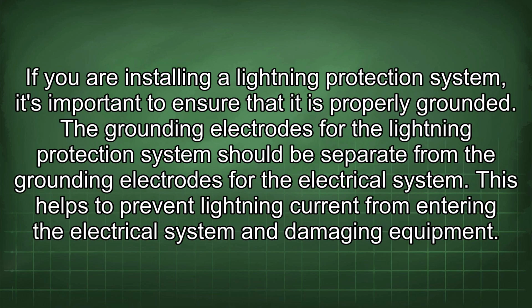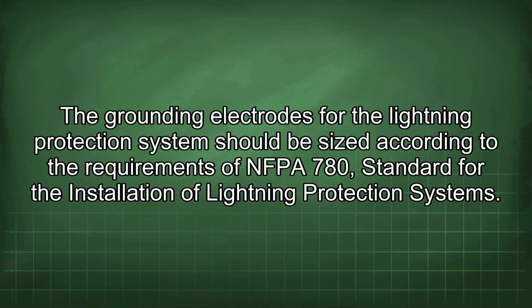If you are installing a lightning protection system, it's important to ensure that it is properly grounded. The grounding electrodes for the lightning protection system should be separate from the grounding electrodes for the electrical system. This helps to prevent lightning current from entering the electrical system and damaging equipment. The grounding electrodes for the lightning protection system should be sized according to the requirements of NFPA 780, Standard for the Installation of Lightning Protection Systems.